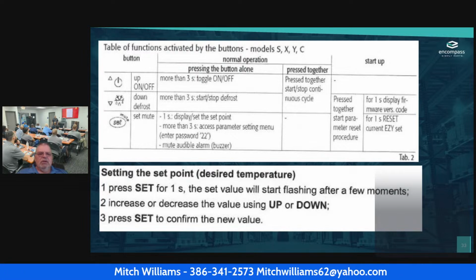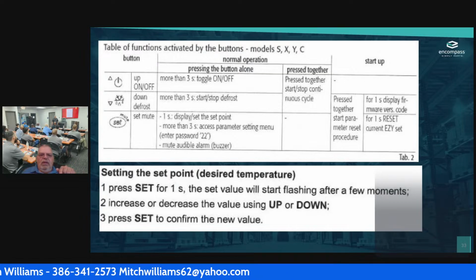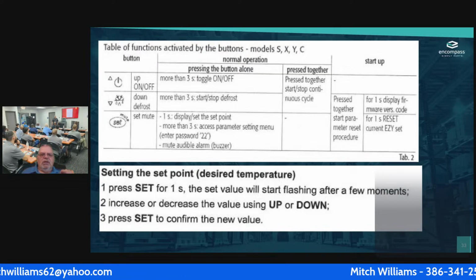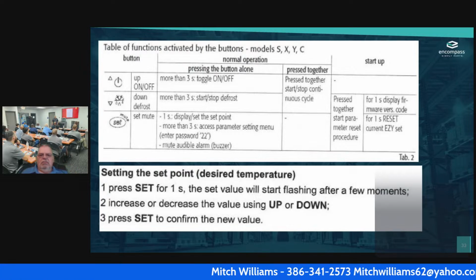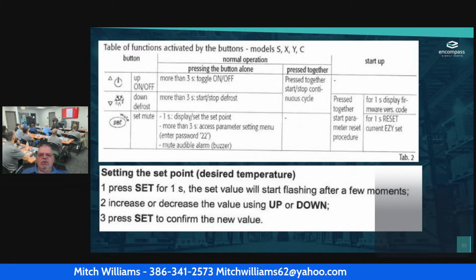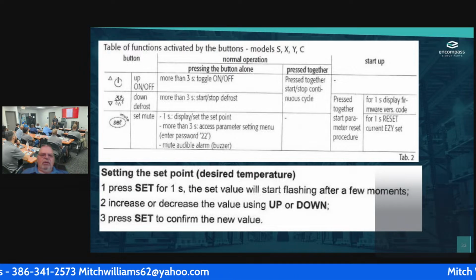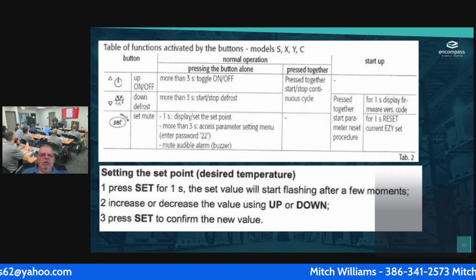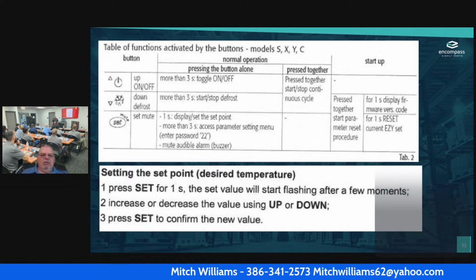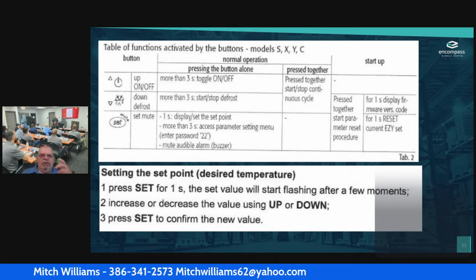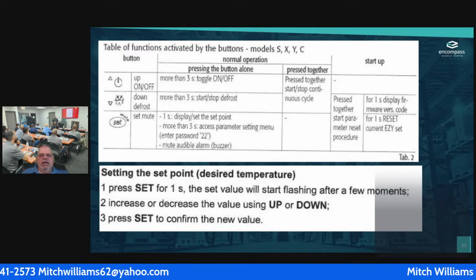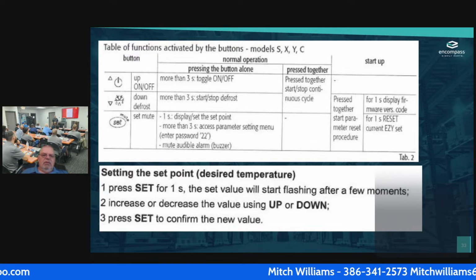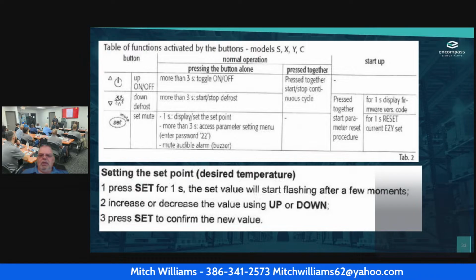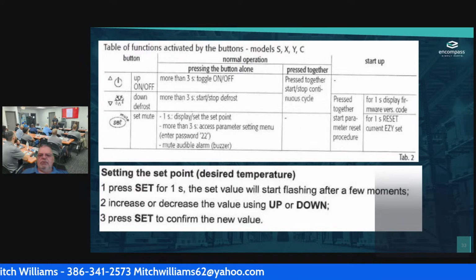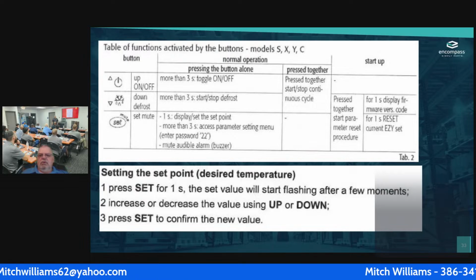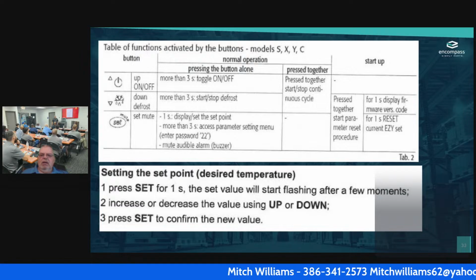Start stop the defrost. So what I can do is hold that down button for defrost, and it will automatically start the defrost. Press together the up and down to start and stop the continuous cycle. If I push both the up and the down arrows, if I want to mute it, I can set the mute, and that 1 second is the display set point. More than 3 seconds, I access the parameter settings. Then the mute audible alarm buzzer. Okay. Press together for 1 second to start the parameter reset procedure. And then if I want to, I can reset it, do it for the same thing.